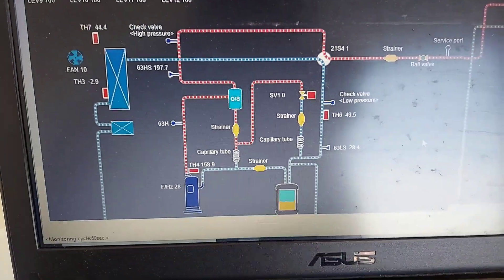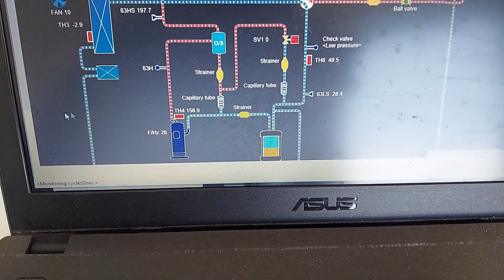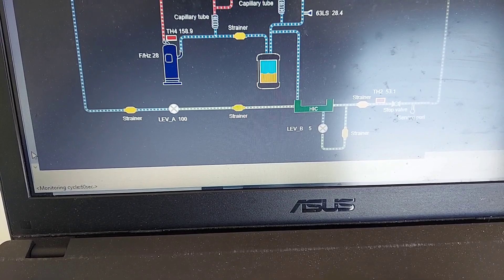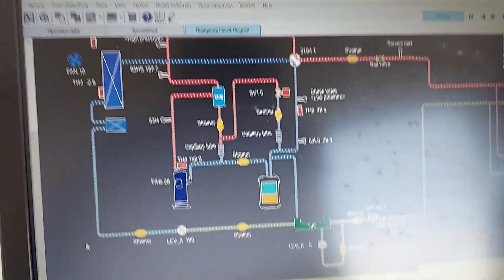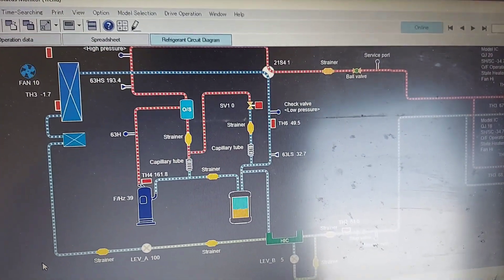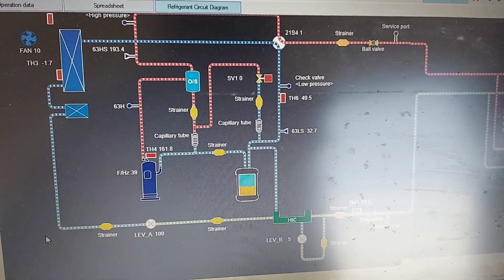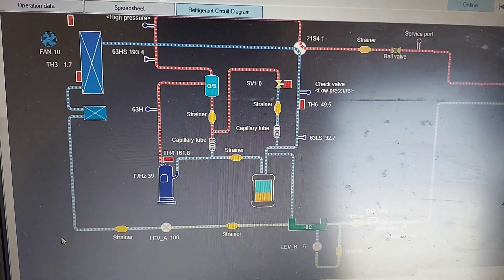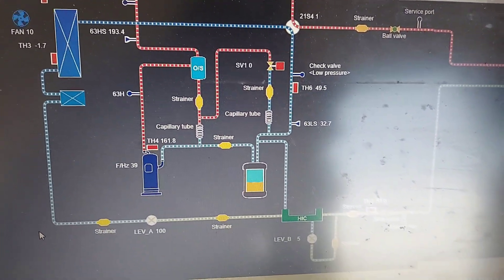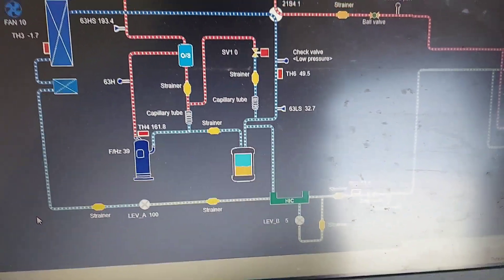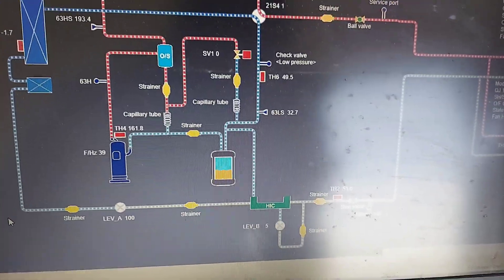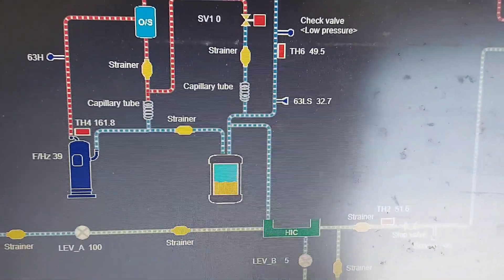This thing is low refrigerant. I'm going to go up to the condenser and we'll add some refrigerant just to confirm. Potentially, most oftentimes people don't know how to properly charge these systems, so they'll just under charge them. And I find it a lot, so not always is a leak, sometimes there's a leak, but oftentimes people just don't know how to charge them, you know, or properly charge them.